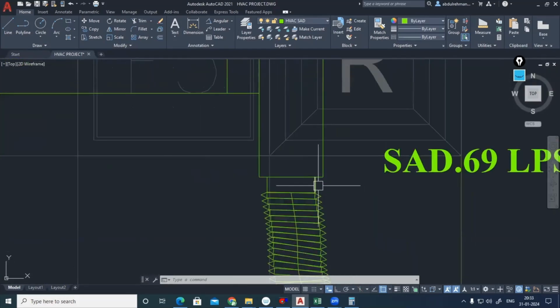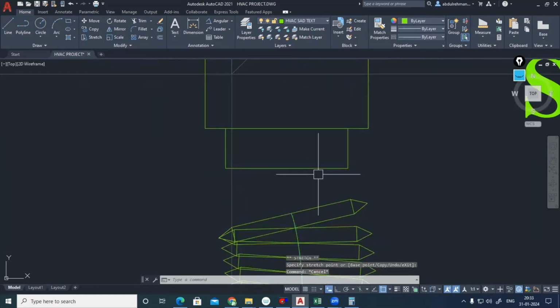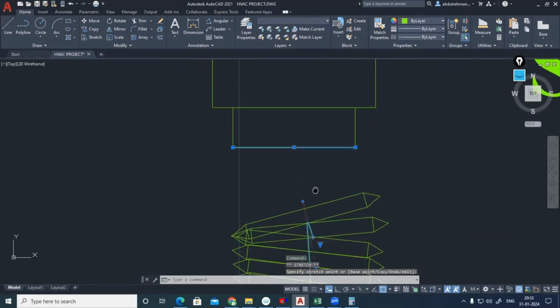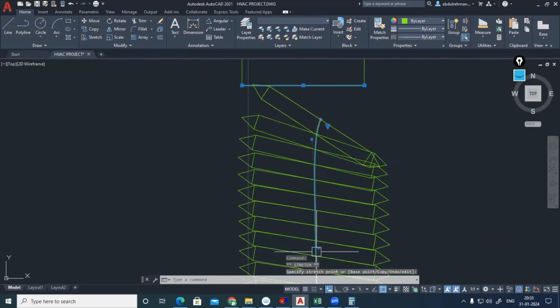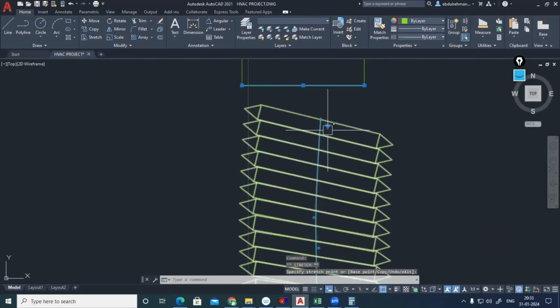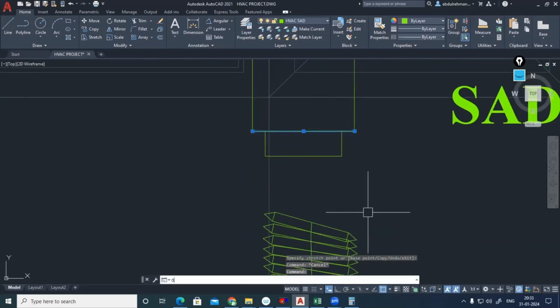Correct. Because this collar length should be minimum 150, no? 150 there. Correct. If you want to provide an RVCD, volume control damper, the length should be minimum 150 we should provide. Same as the diameter of flexible, the same length we should have.